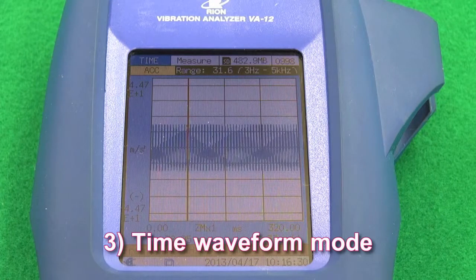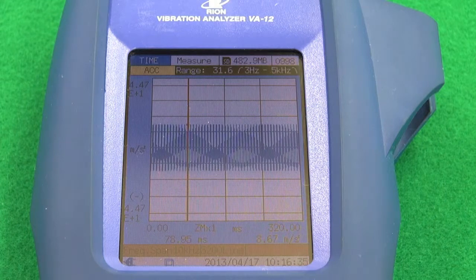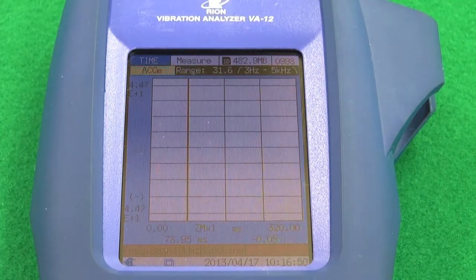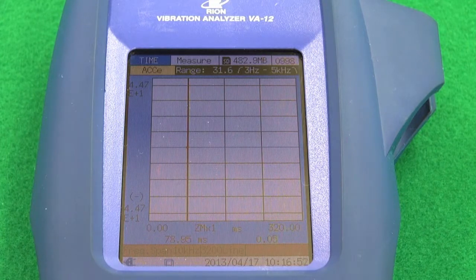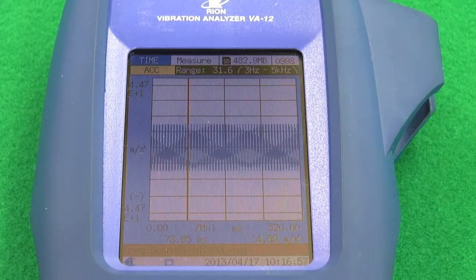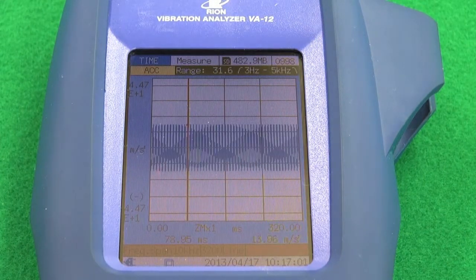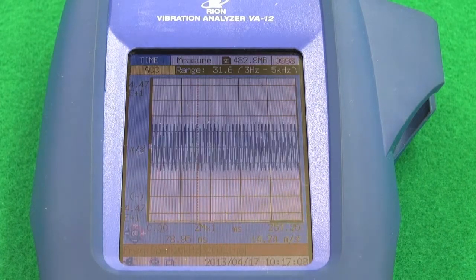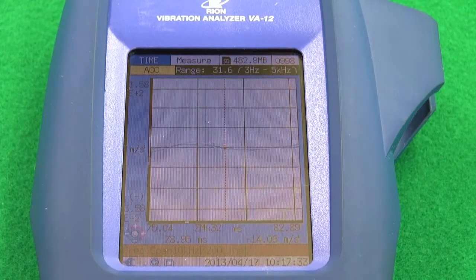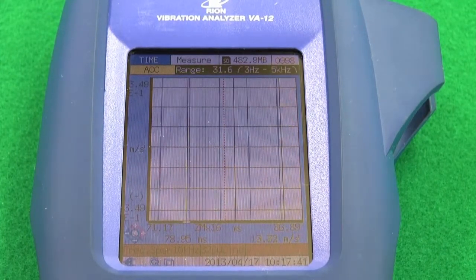Feature 3: Time waveform mode. In time waveform mode, acceleration waveforms, velocity, displacement and acceleration envelope curves can be displayed using up to 8192 samples. The time waveform display, like an oscilloscope, has a time axis which can be magnified up to 32 times and a magnitude axis that can be magnified up to 16,384 times.